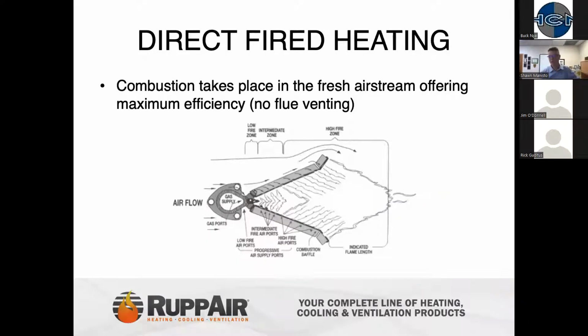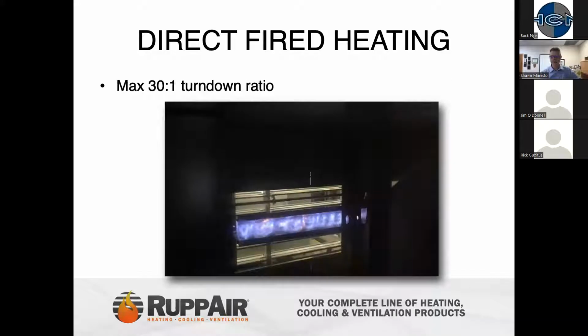This is just a cross-sectional area of what a direct fired flame looks like. Unlike the indirect fired units, where you have a heat exchanger heating the air and a flue that dumps the flue gases out into the atmosphere, in this case the combustion exists within the fresh air stream. As the fresh air comes from outside, it goes across this open flame burner, and basically all the heat is utilized in the building. No flues or vents needed on this product.